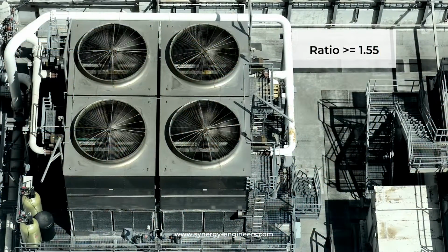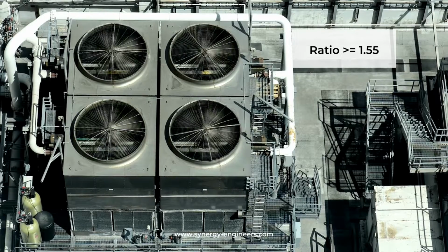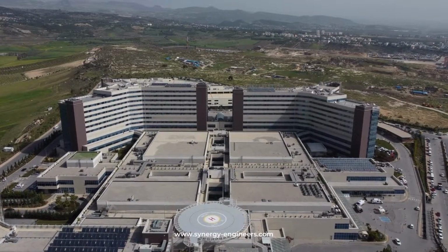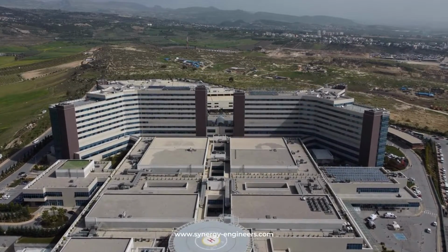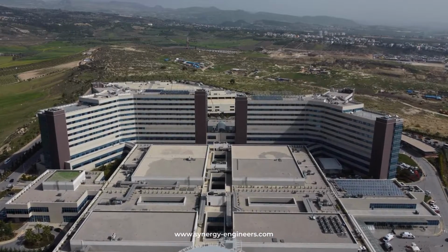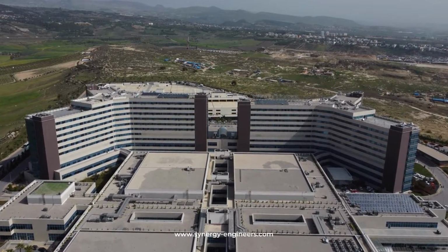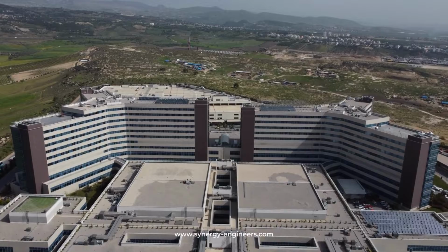So studies of these systems have proven that when there's a ratio of the sides of the array to the number of fans and impeller diameter, if that ratio is greater than or equal to 1.55, there's typically no loss of performance. That's because when that ratio is at that level or greater, it really provides enough space around the fan impellers for the airflow to fully develop and helps negate any system effect that might occur.